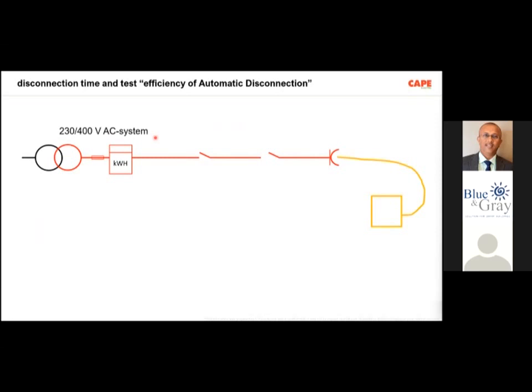Now, what do we mean by disconnection time? In your electrical installation, you have a transformer, you have the meter board, and then you have the fixed part of your electrical installation. Up to the meter board, if you are getting a public electricity supply, the disconnection time is fixed by the energy supplier. In most of the European nations and America, a fixed rule exists, whereas in India, there is no rule. So even in case of a fault in the public distribution, it may exist for several days or even sometimes months. Whereas foreign countries, developed nations, have a clear rule. So the fault shall not exceed, let us say for example, 1 hour.